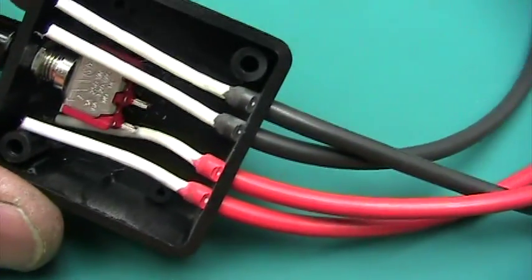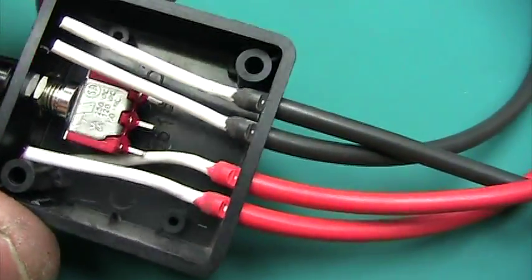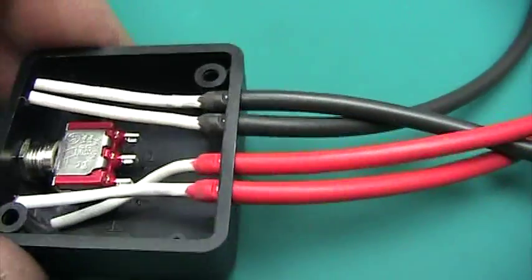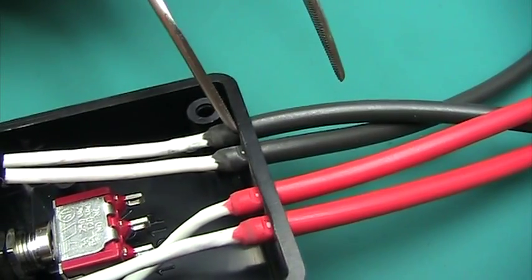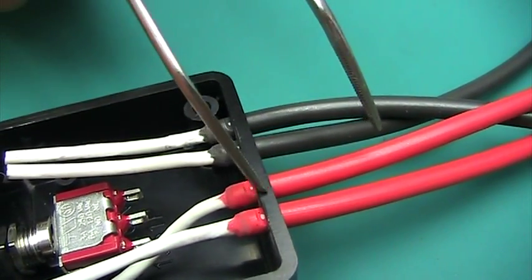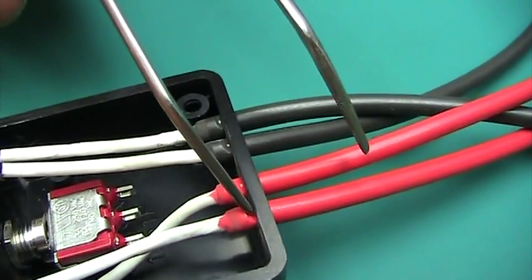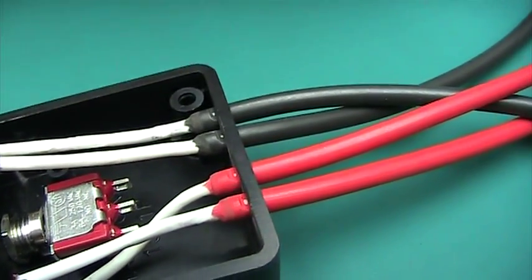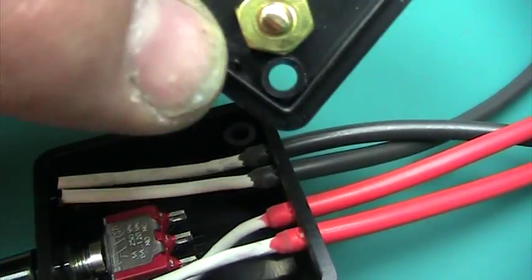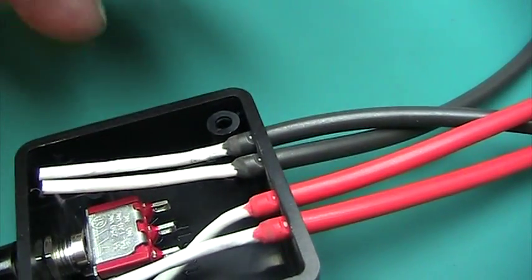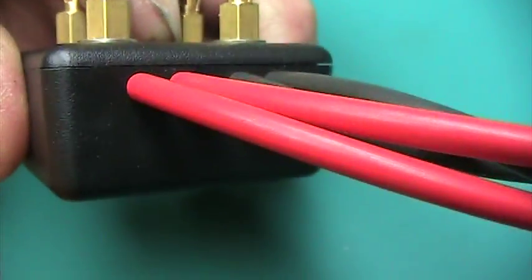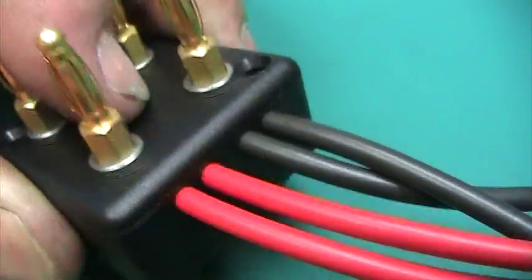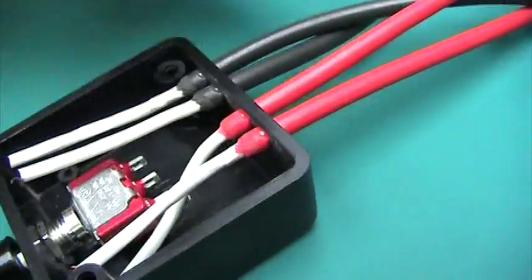Here's the box with these silicone leads pulled through. They're actually kind of a press fit in there, stretched in. Then I have a little notch ground right there into the silicone outer shell, not down to the white inner shell, that matches up with the lip on the case. So when the case piece goes in like this and engages, it actually latches into that notch in the silicone to keep it from being pulled out. Not bulletproof, but plenty good enough for careful lab use.